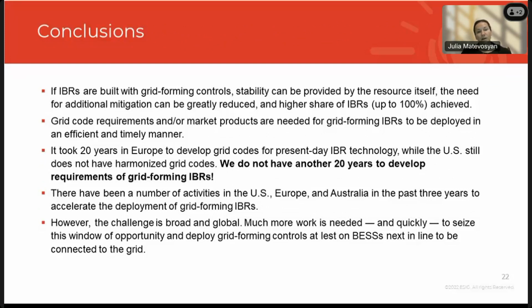Grid code requirements and market products are needed for grid forming inverter-based resources to be deployed in an efficient and timely manner. It took 20 years to develop grid codes for existing grid following inverter-based resources, and we don't have 20 years to do the same for grid forming. There are a number of activities happening in the US, Europe and Australia that hopefully will accelerate deployment of grid forming inverter-based resources, and hopefully will lead to more harmonized specifications from the get-go. And the challenges are broad and global.